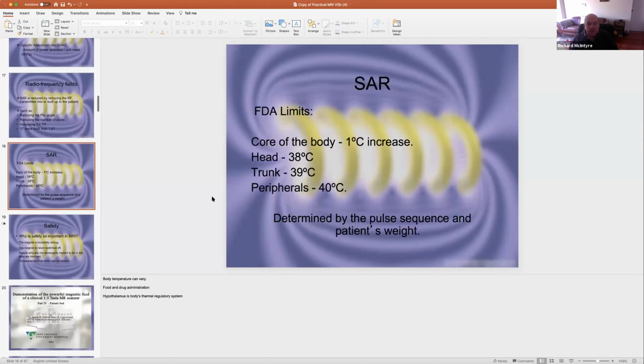The core of the body can go up by 1 degree. The head can go to 38 degrees, so 37.7 can go up to 38 degrees. The trunk, the machine will let it go up to 39 degrees, and the peripherals can go up to 40 degrees. All this is determined by the pulse sequence and the patient's weight.